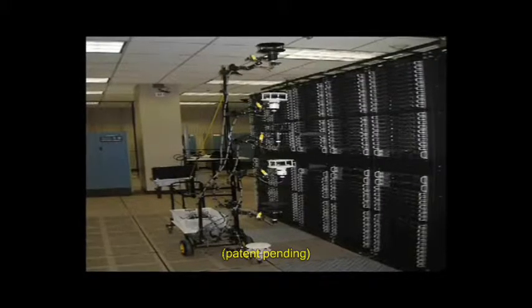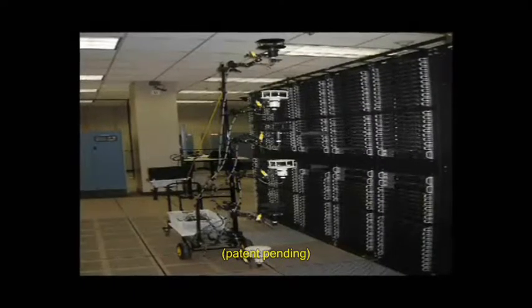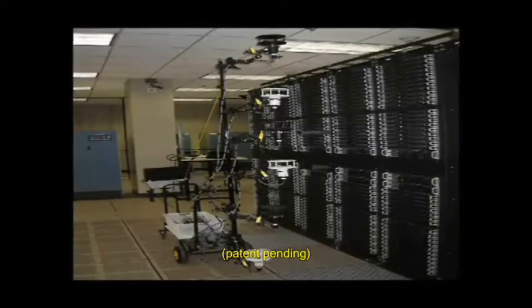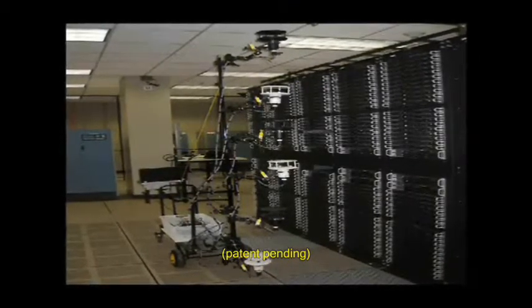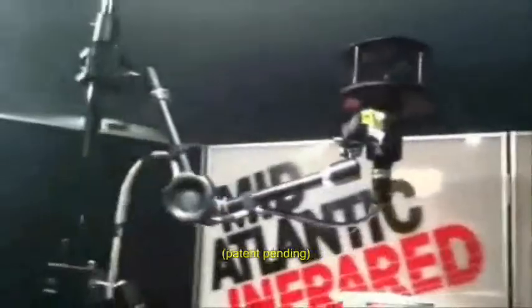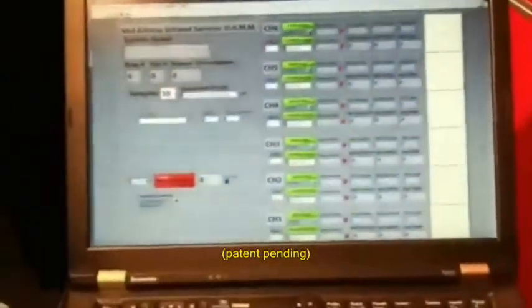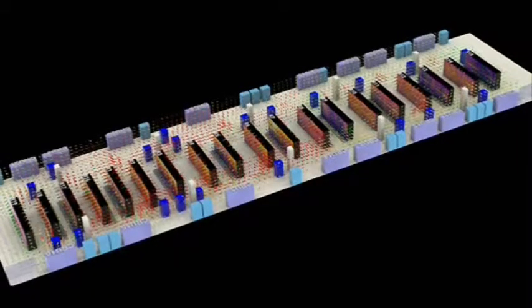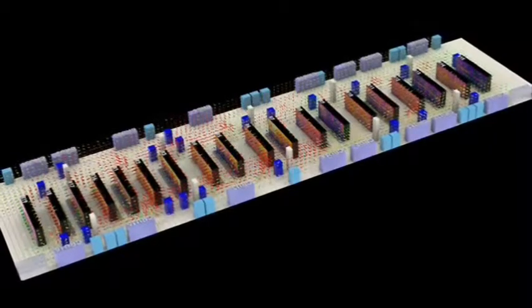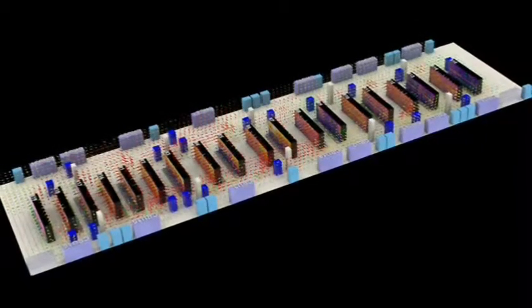The key feature of the Data Center Airflow Measurement and Mapping tool is its special sensors which measure both air velocity and direction accurately at very low air speeds. The tool allows us to create our multi-dimensional vector field graphics which detail airflow characteristics. Our custom designed program performs analysis on rack inlet air property data to calculate metrics such as rack supply and return heat indexes and even rack power dissipation. The DAM tool is pushed through a data center with readings taken at each tile. Each reading takes only seconds, so comprehensive studies of the largest data centers can be conducted quickly.